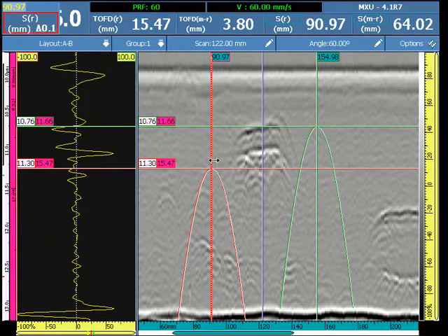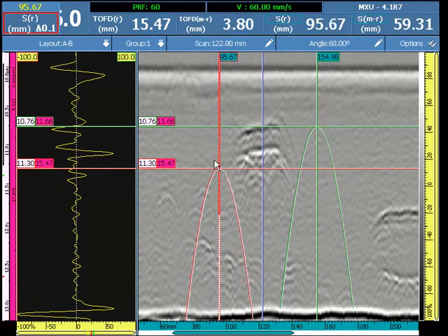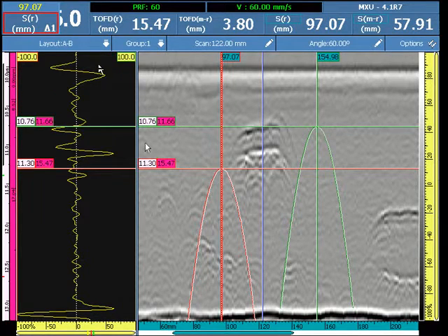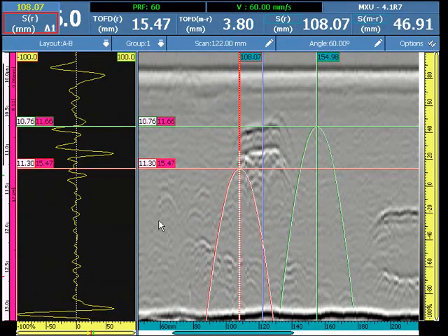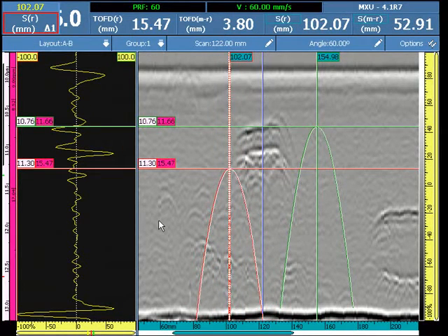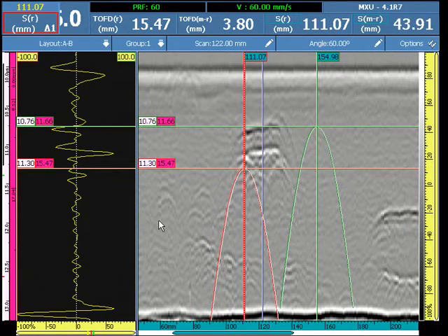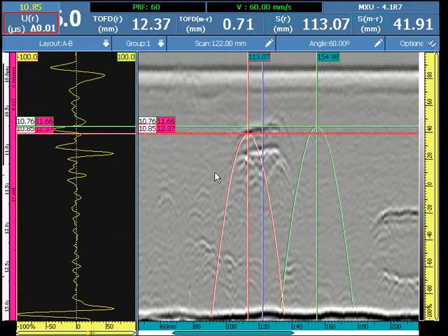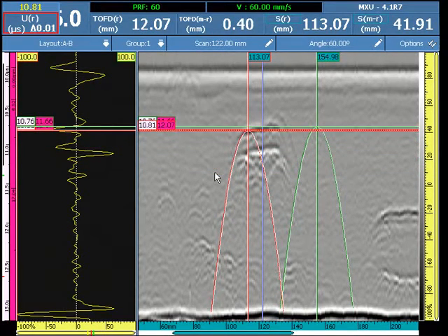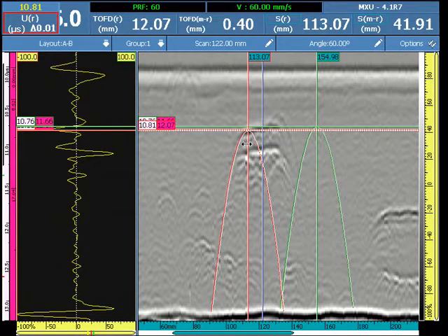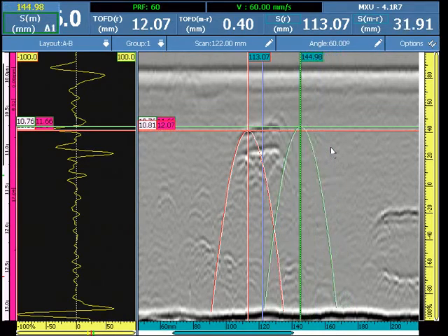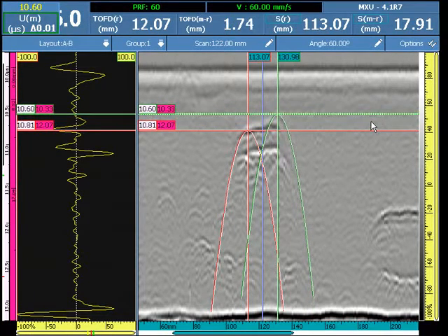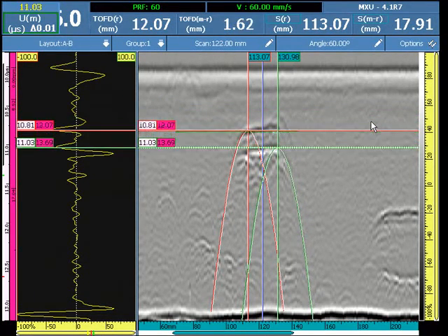We'll define the length of the flaw first. As I move the cursor — to change the resolution, spin with the rotary knob using a touch and hold or right mouse click — we will bring the cursor to the approximate edge of the flaw. We'll use our parabolic cursors to align with the edge of the parabolic shape, and do this with the reference cursor as well. We can see the measure cursor aligning with the far edge.